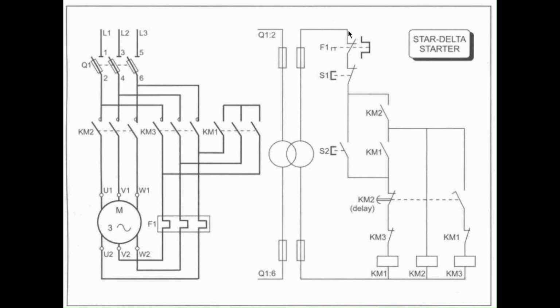If we follow round, this is now closed. This is energized, which is a contactor. This closes this contactor. Also, this side is energized, KM2, which is the main contactor. So what that means is now we have supply current coming in this way, coming out through the overcurrent relay, and then through the KM1 contactor.